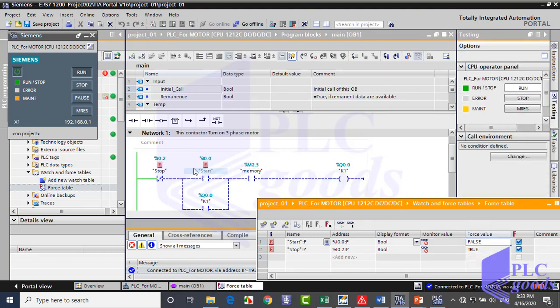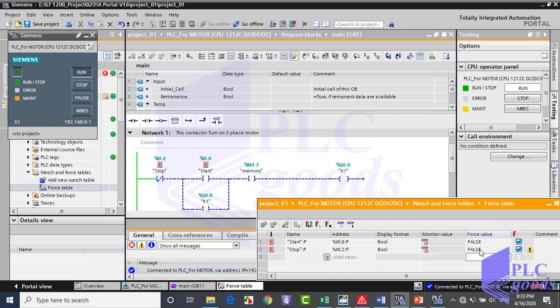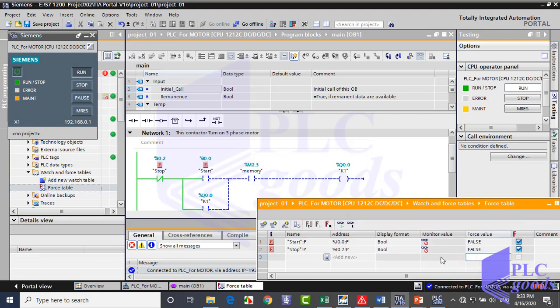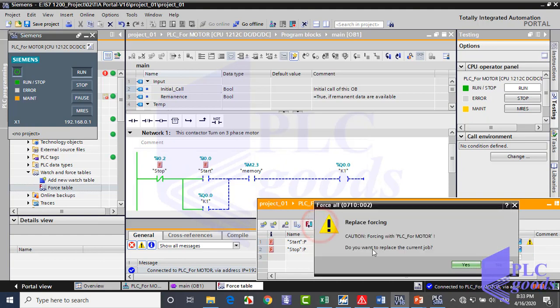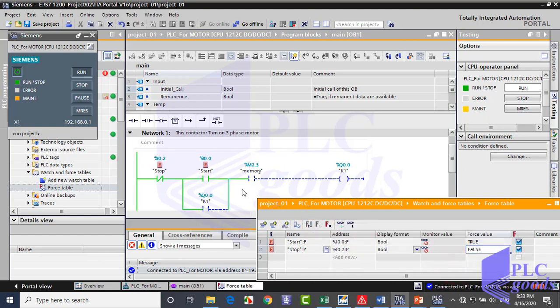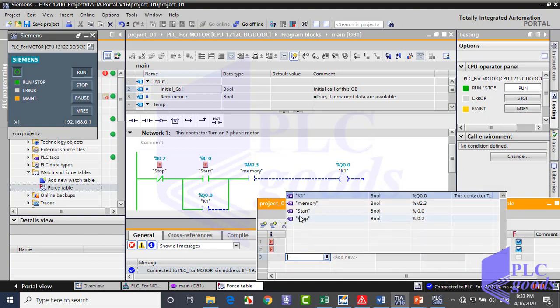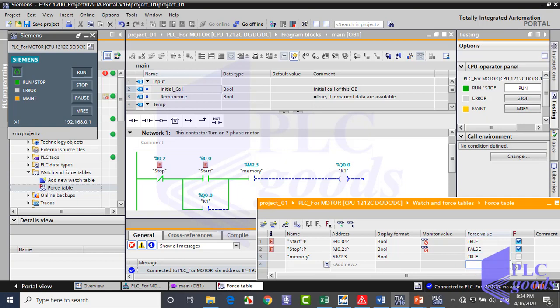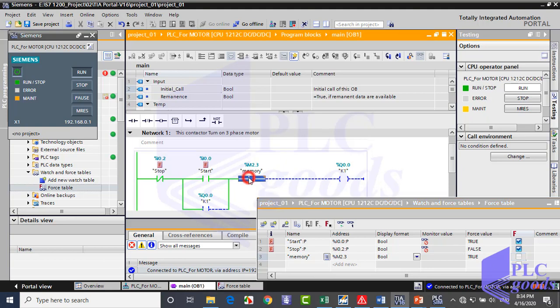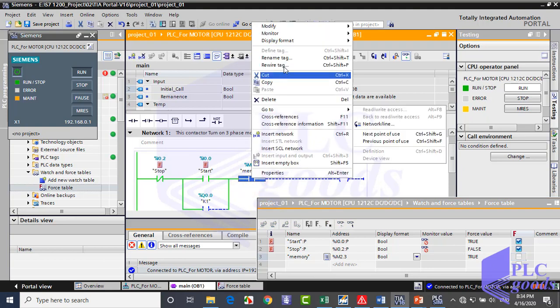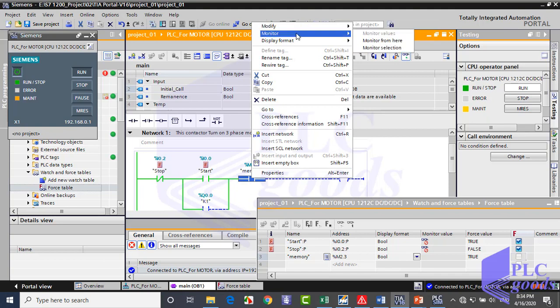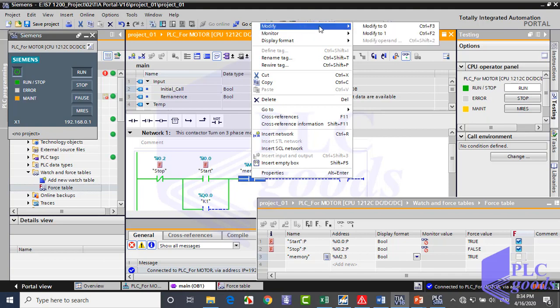Now change the start contact from the force table. If we want to turn on the output, we need to change this normally open contact with an address from memory to close. But we can't do it from the force table. For contacts which have an address of CPU memory, right-click on that contact and here modify its value to 1 or 0.